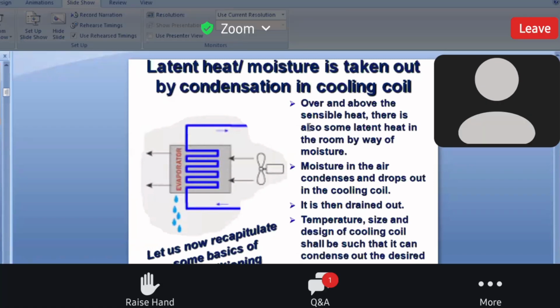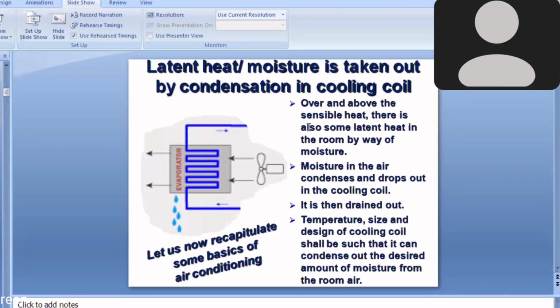The latent heat part of the heat load is not taken away by the supplied air. The latent heat is taken out by condensation in the cooling coil. Latent heat means water vapor, moisture in the air. So when the air passes through a cooling coil, the moisture condenses and comes out, and we drain the condensed moisture out. The temperature, size, and design of the cooling coil shall be such that it can condense out the desired amount of moisture from the room air.